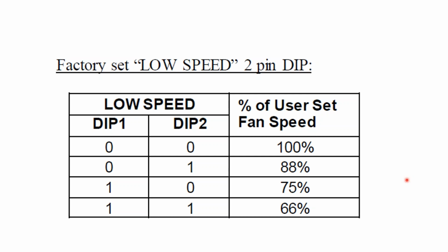And that came up with your voltage range, which we set with the rotary switch and your slide switch. And then once that was done, if you're on a two-stage unit, now we need to set up the low speed. So that brings us to the slide. If it's a three-phase unit, we're just going to have these two dip switches. And now we set the low speed up. Where do we want our low speed at? Do we want it at 100% of what our setting was on the ABC switch and potentiometer, or do we want it at 88%, 75, or 66%?